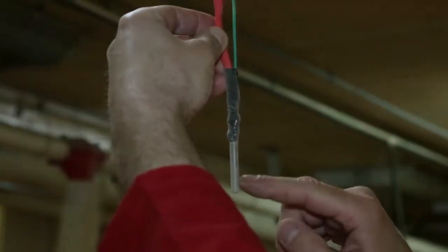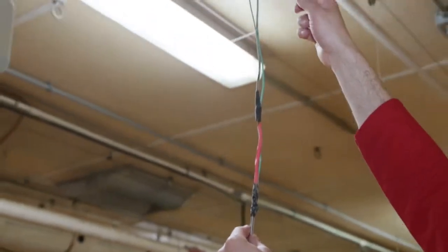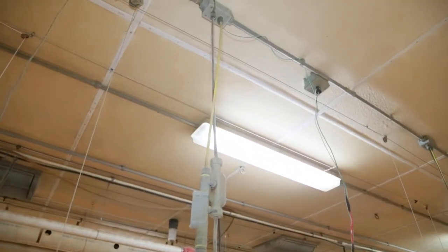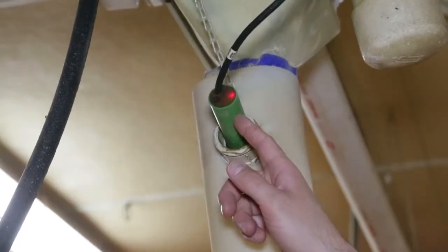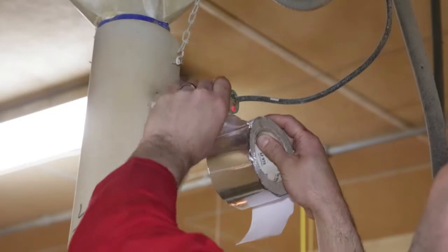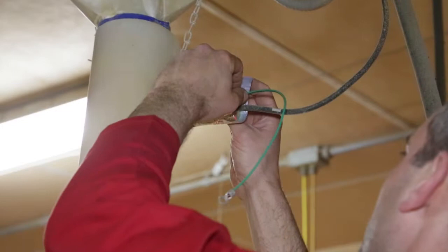If a sensor has a metal tip and you cannot clearly determine that it is grounded, attach a ground wire securely to the tip with a hose clamp and ground the tip back to the sensor ground or earth ground. Cover feed sensors with a Faraday cage. Durable foil tape works well. And add a wire to the earth ground. Wrap the foil with electrical tape.